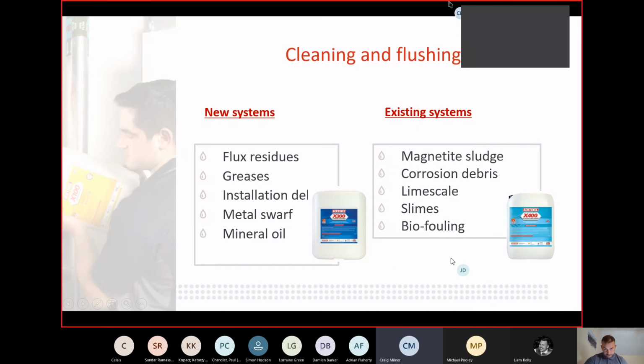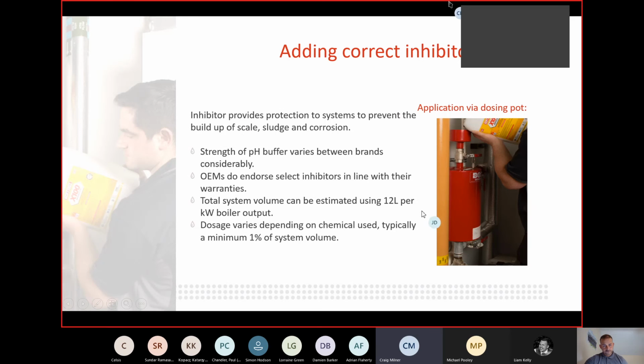That's about removing the magnetite, corrosion, limescale, slimes, and any biofouling - lifting it off the surface and removing it when you flush. A good tip for flushing is to measure the TDS of the incoming main, and then to ensure you've flushed all the cleaner out, get within 10% of the total dissolved solids of the mains water. If you're within that, you know you've got 99% of the cleaner out of the system.